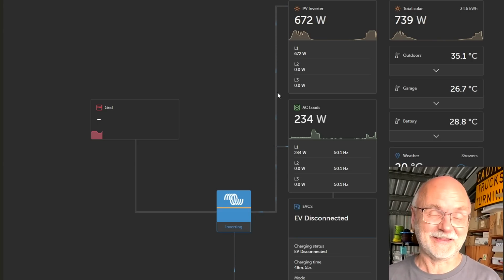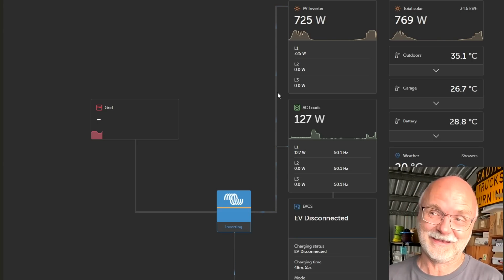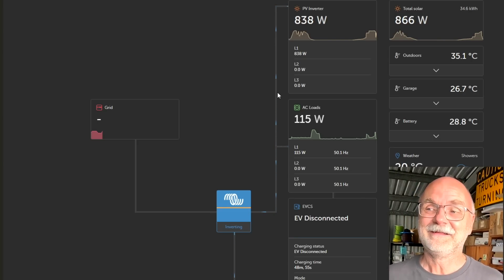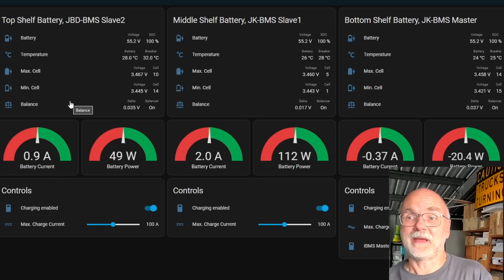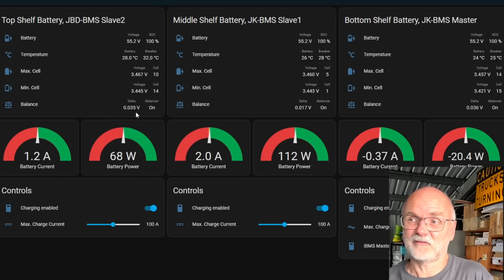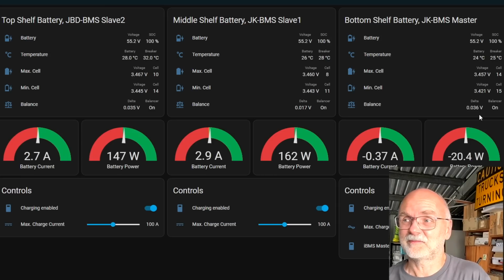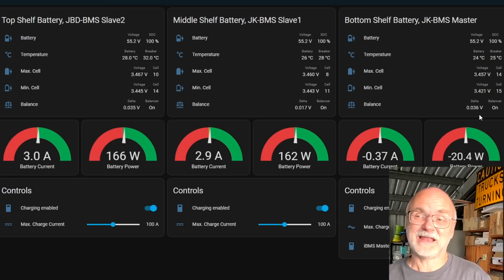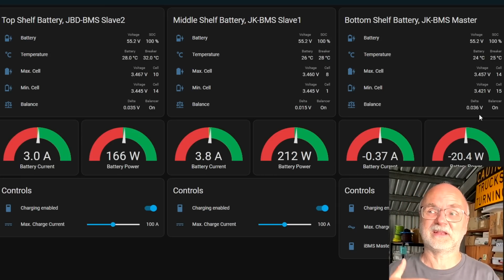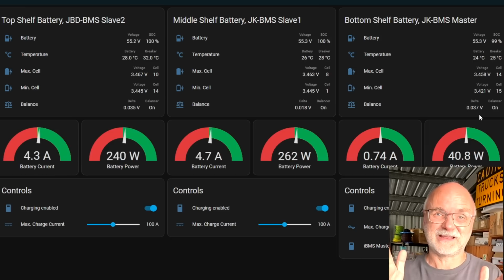Unless I tinkered with the settings, of course, to do a test or whatever, then of course something turns off and the lights go out. So this will be the maximum deviation we will see, 35 millivolt, 17 millivolt, and 36 millivolt here in these BMSs or batteries. And from now on, if I fully charge the battery every single day, the deviation will only go down because it gives the balancer more time to do its job.